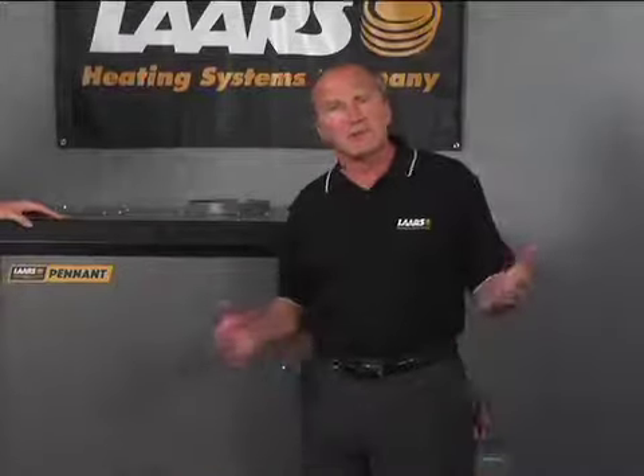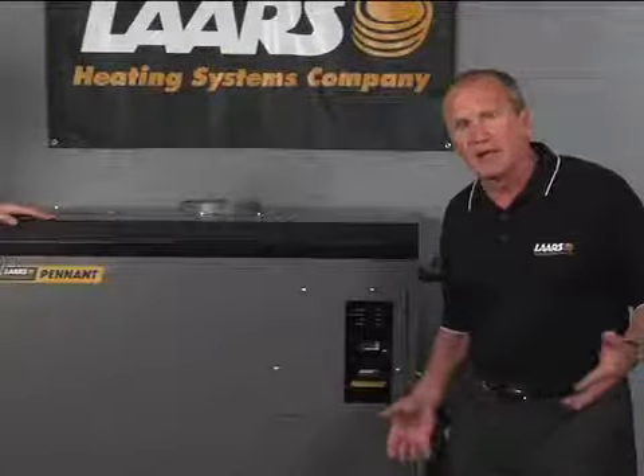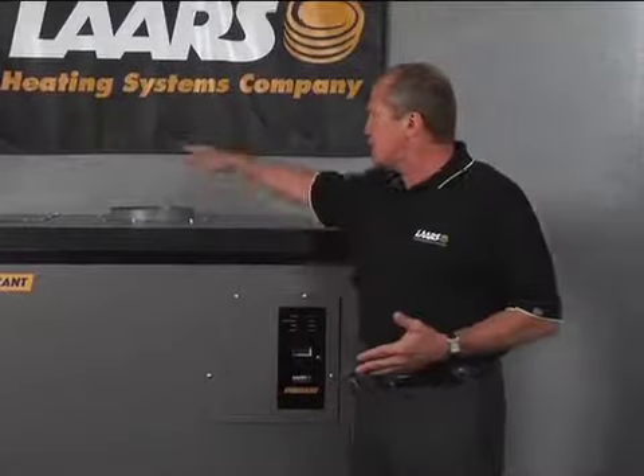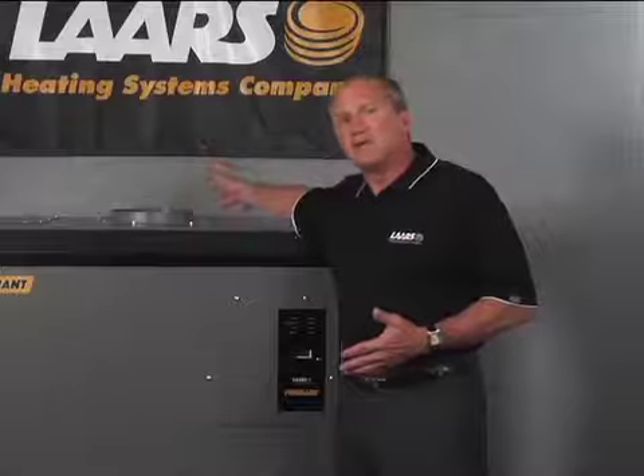For those of you in warmer climates where you want to put the boiler outside, you can do that. We have termination kits that set on the top and or the back of the unit, so you can terminate the boiler when you use it outside, so no rain or any other weather-related problems hurt the boiler in any way. We install a lot of these outside and in those climates where it's more acceptable to do that.